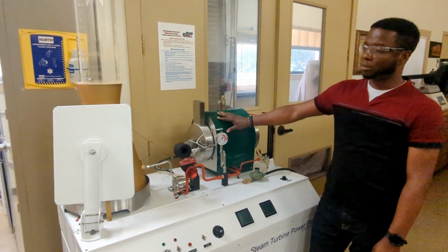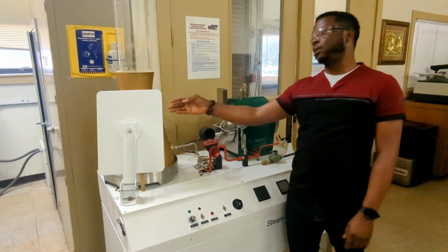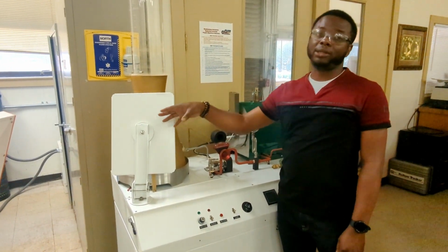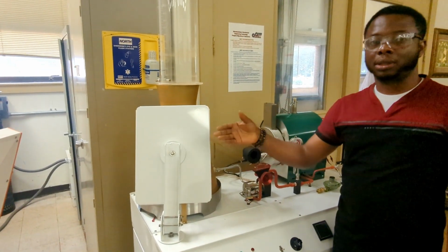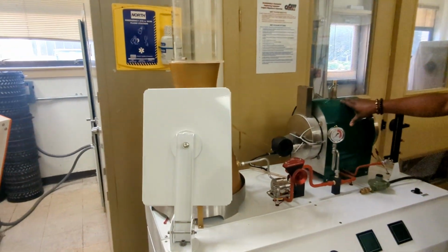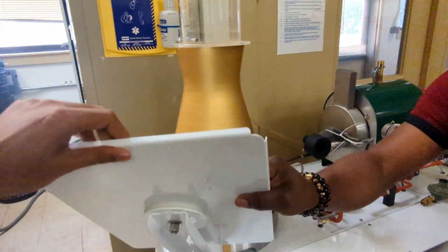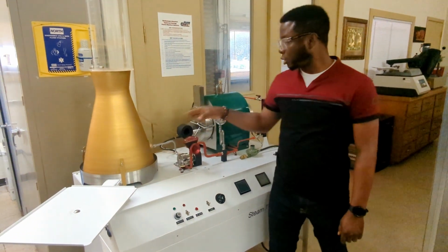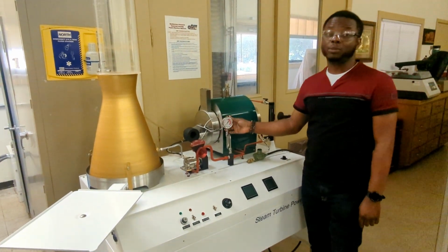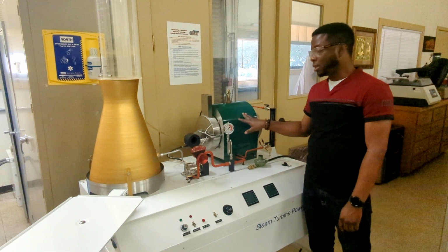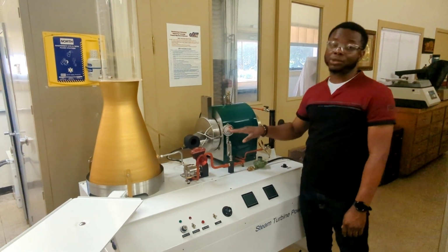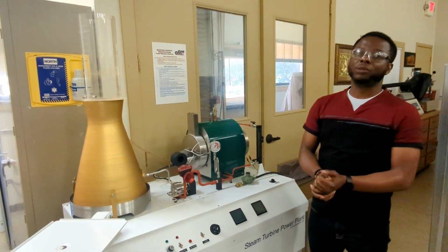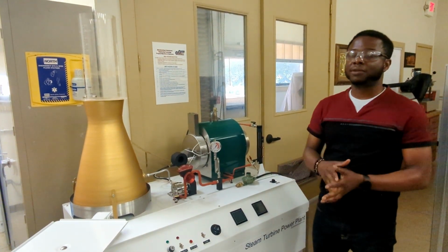And with that, we can use our laptop, the software embedded in it, so we're able to monitor what's going on inside the system. There's always a connected laptop here that's going to be placed here. It helps us to monitor the built-in pressure inside the boiler. We want to achieve the pressure of 120 psi, and this can take up to 2 to 5 minutes.